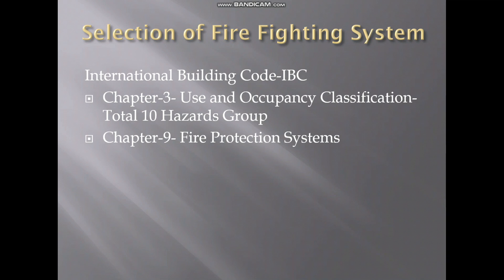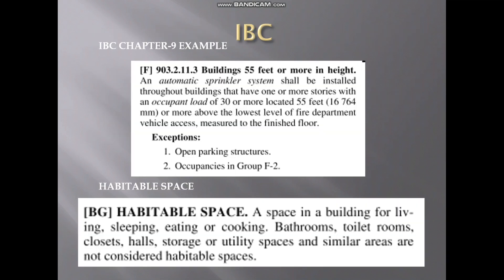For example, IBC chapter 9 defines that we need to provide an automatic sprinkler system if the building height is 55 feet or more. So the first step of this exercise is to identify the building's habitable height.